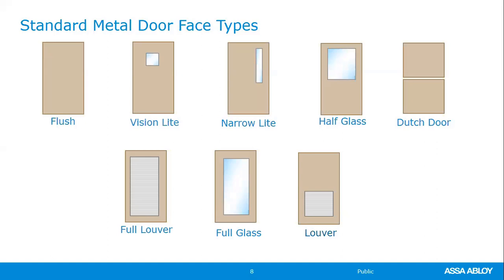The factory will not ship full glass doors with cutout only. For fire-rated louver doors, you must have a fusible link louver — there's a link that disintegrates when heated to a certain temperature, allowing the slats to close. On a fire-rated door, the louver can only be in the bottom half of the door. If the door is non-rated, you can put multiple louvers anywhere. Just be aware of those stipulations when it's a fire-rated door.